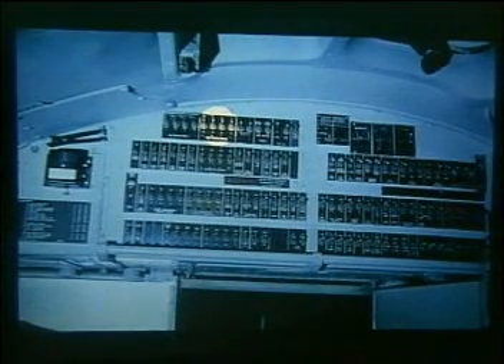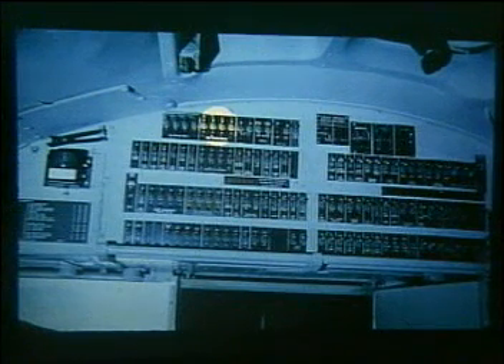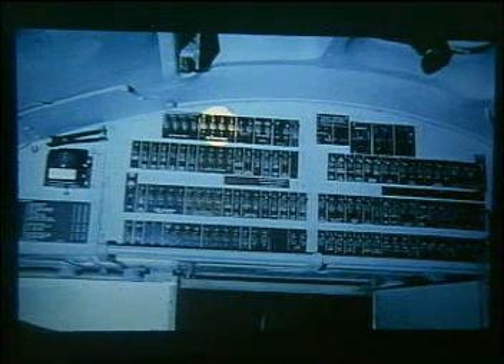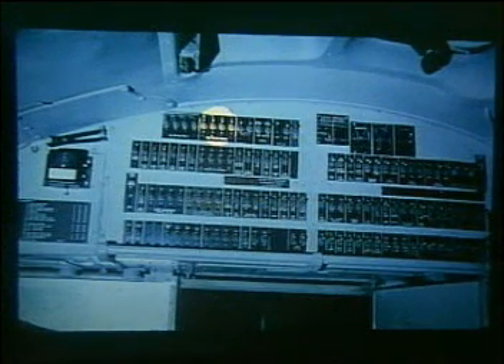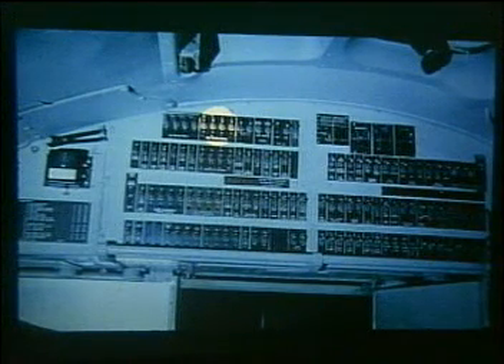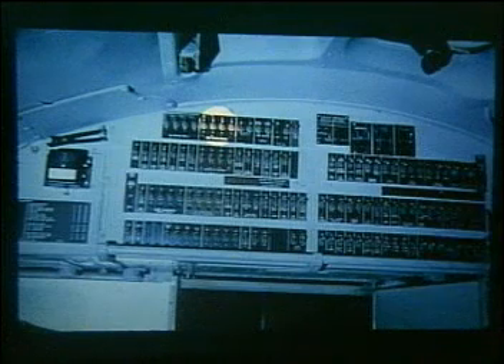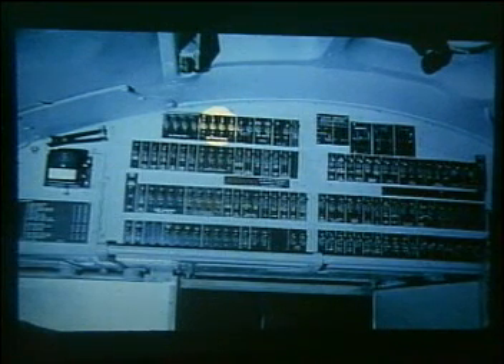The generator control circuit breakers, highlighted here on the master junction box, protect the bus from a malfunction or short in the generator control panel and the generator. It provides a source of power to the generator control panel to be used as a reference voltage. This enables the generator control panel to connect the generator to the master bus.